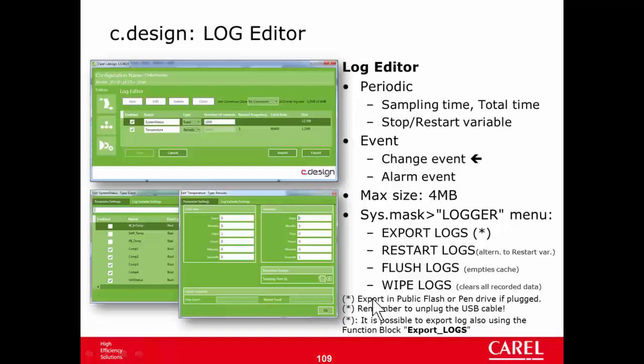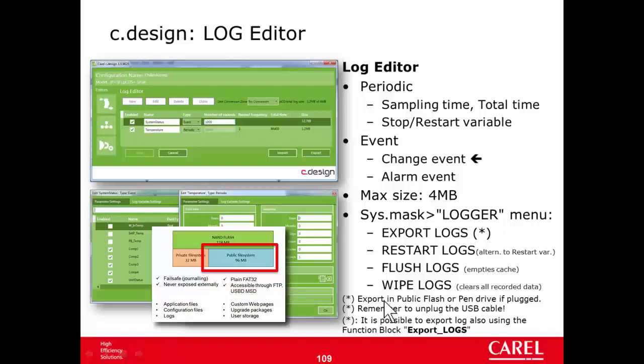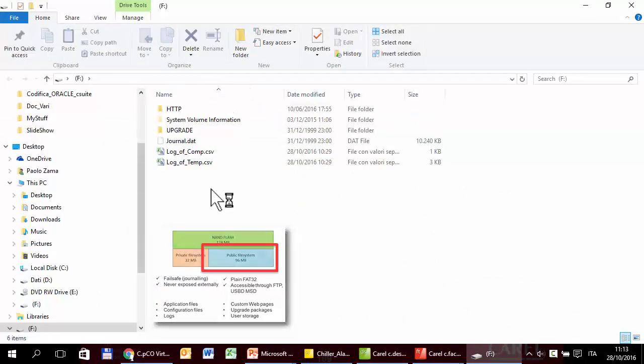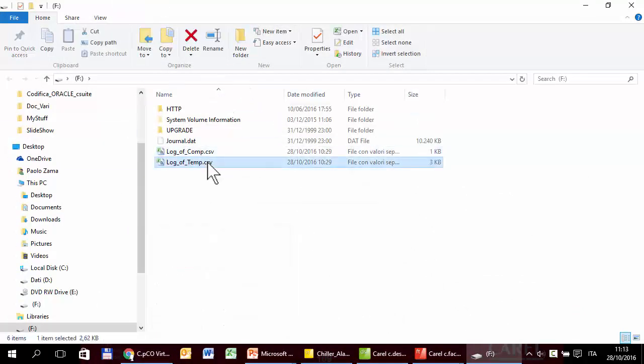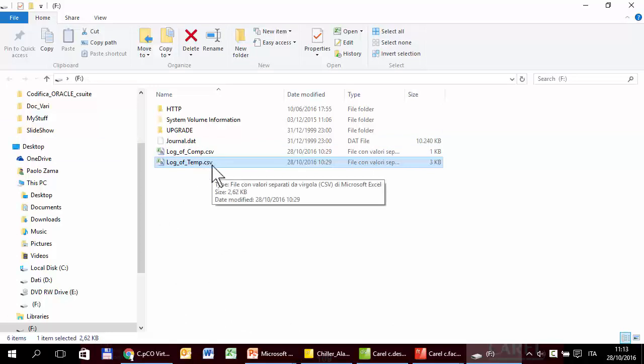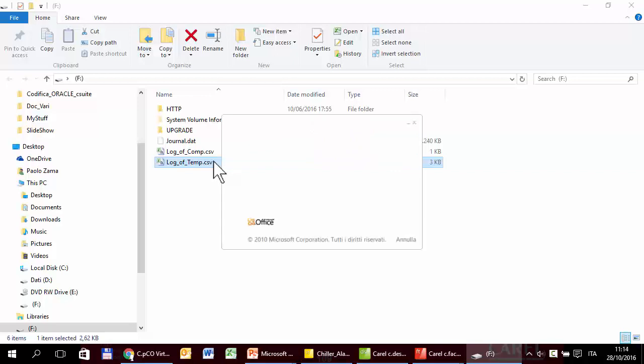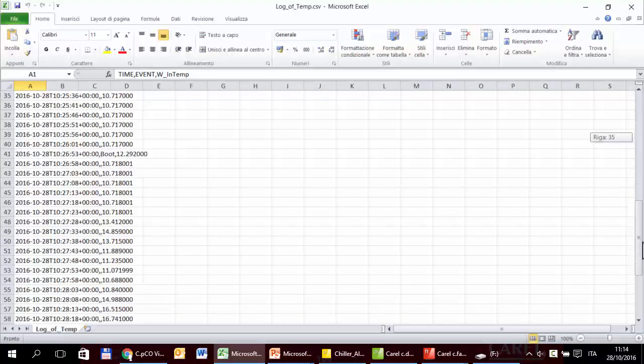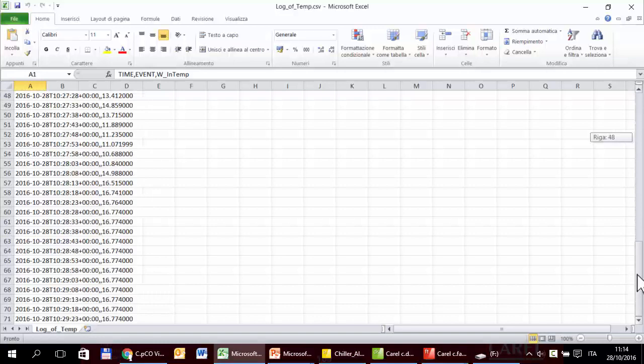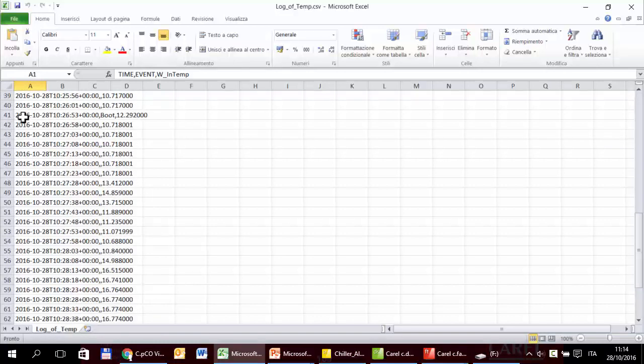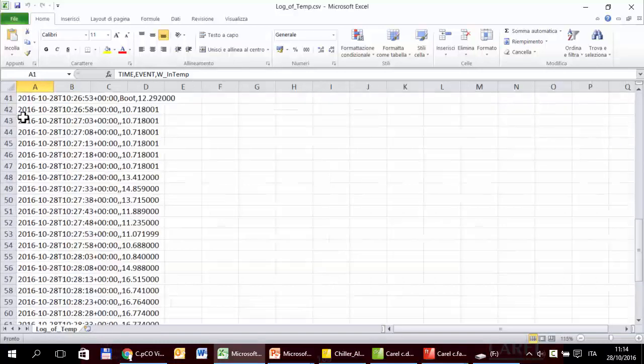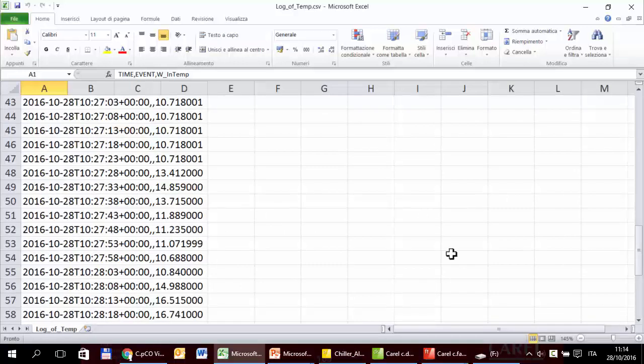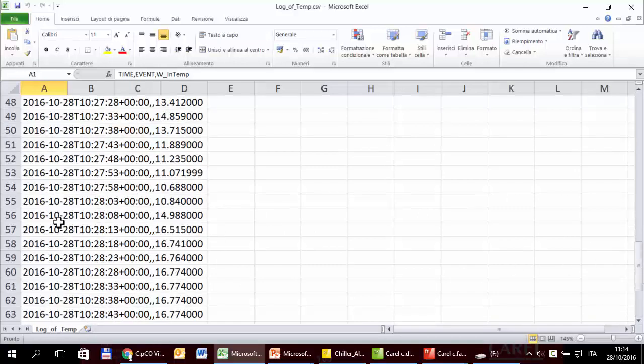In this moment, there isn't a pendrive plugged in the controller. So it has exported in the internal public flash. So now I'm connecting the controller to the PC via USB cable. So this is the internal memory, and here are the two files that it has exported. They are in standard CSV format, that is a text file. We can open via Excel, but also with notepad. So here are the logs. This is today. The timestamp is in a standard format. The timestamp and the value of the variable.